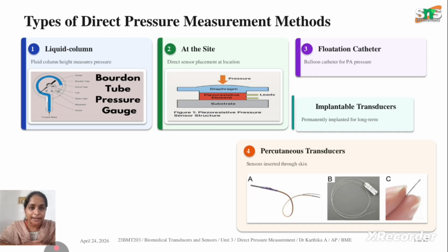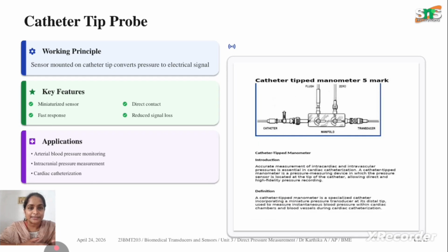See the types of direct pressure measurement methods. The first one is liquid column, the second is catheter type, and the third is flotation catheter type, and we have implantable transducers as well as percutaneous transducers. Now the catheter tip probe. The working principle is a sensor mounted on the catheter tip. It converts pressure into an electrical signal. This electrical signal is further amplified and processed for our instrument input.